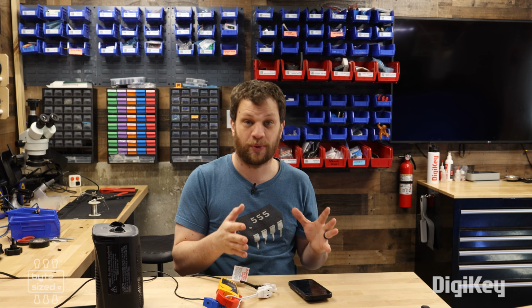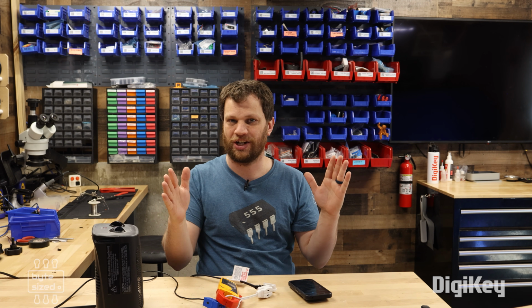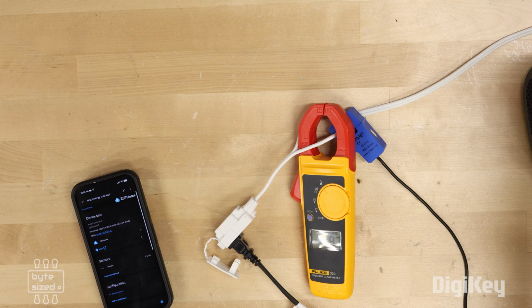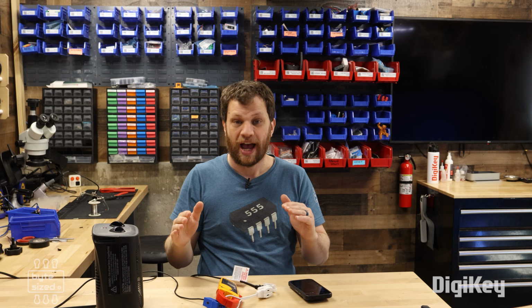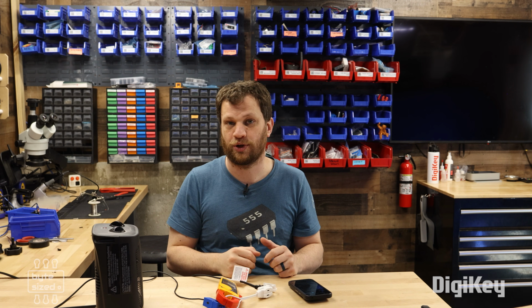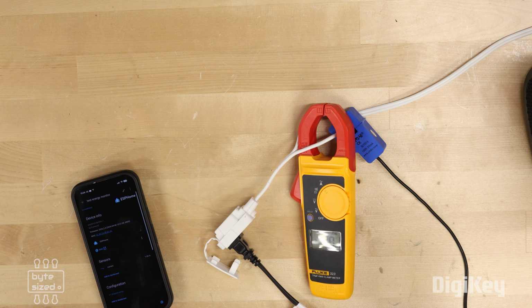So we've got a change here, which is good, but that linear interpolation is off, so we need to calibrate it. I'm going to let the space heater settle into its steady state and then measure that current using the Fluke meter. Right now it's at about 10 amps.